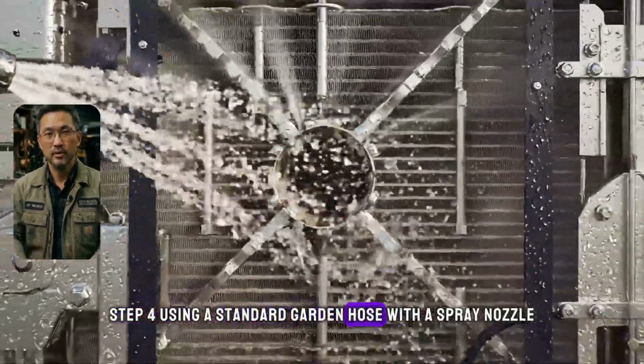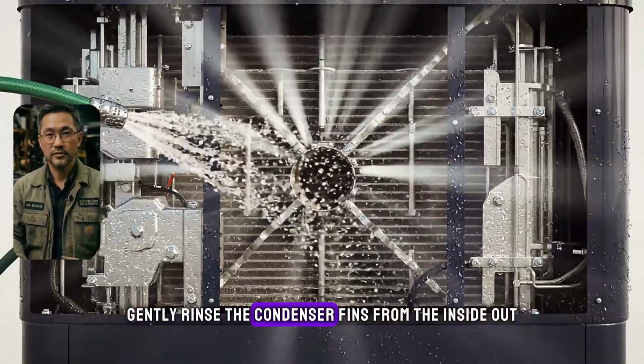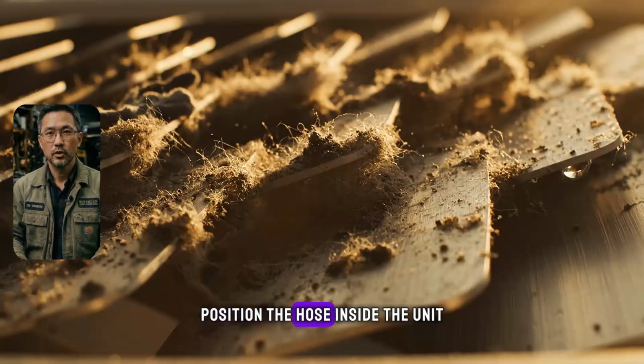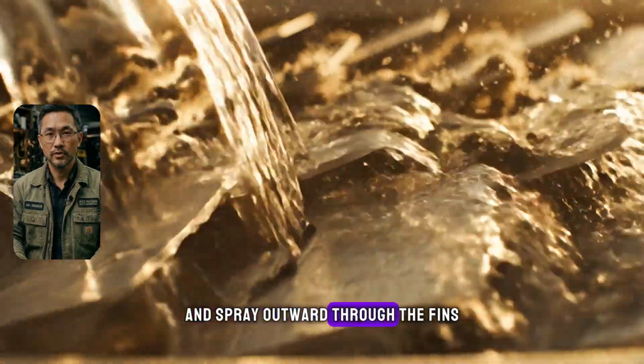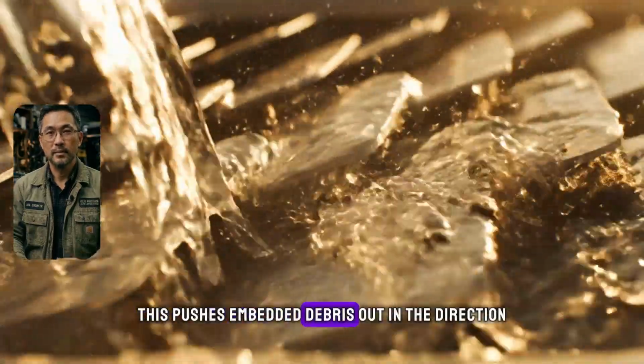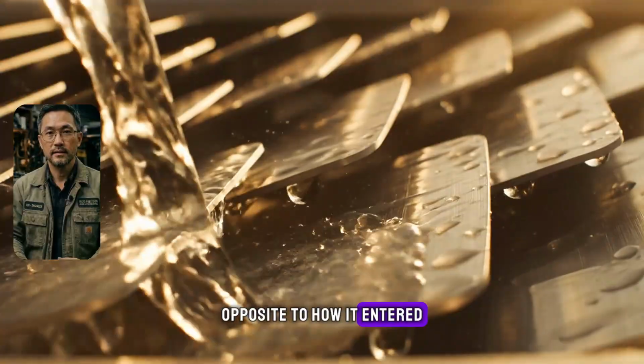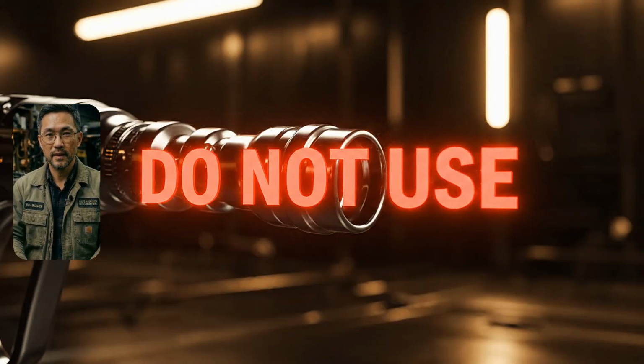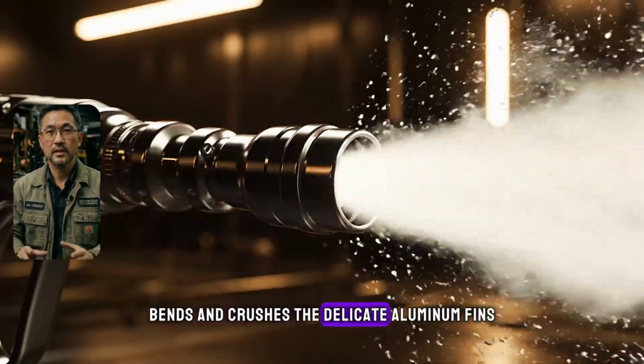Step 4. Using a standard garden hose with a spray nozzle, gently rinse the condenser fins from the inside out. Position the hose inside the unit and spray outward through the fins. This pushes embedded debris out in the direction opposite to how it entered. Do not use a pressure washer. High pressure bends and crushes the delicate aluminum fins, which restricts airflow permanently.